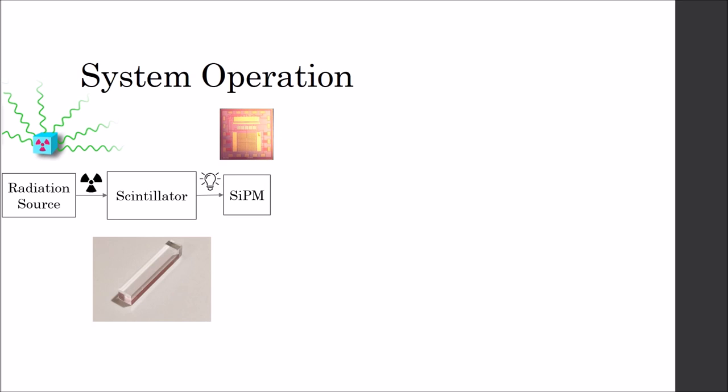The light emitted from the scintillator will then be captured by the silicon photo multiplier. The silicon photo multiplier is the first step into the control circuit. It's a small chip with a small window at the top. It receives the photons emitted by the scintillator, and through breakdown events, creates current pulses, which are sent to the control circuit.